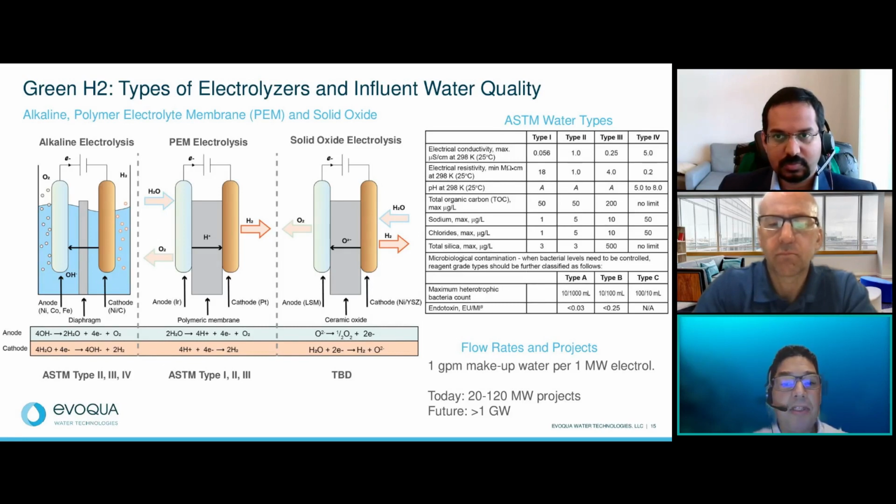For an industrial process, let's give the example of something in the Gulf Coast. If it's a petrochemical plant, it's taking surface water from a river. Clarification, multimedia, and ultrafiltration are becoming very popular because of advancements in technology. So we could filter water from a river, pass it through an ultrafiltration system, and that ultrafiltrated water can go into a cooling system. That can be a typical application for cooling, and of course, all of this in the context of hydrogen. Now, after it goes into the cooling, obviously you have all the chemistry, 5 to 7 cycles is common, and then the water needs to be treated.